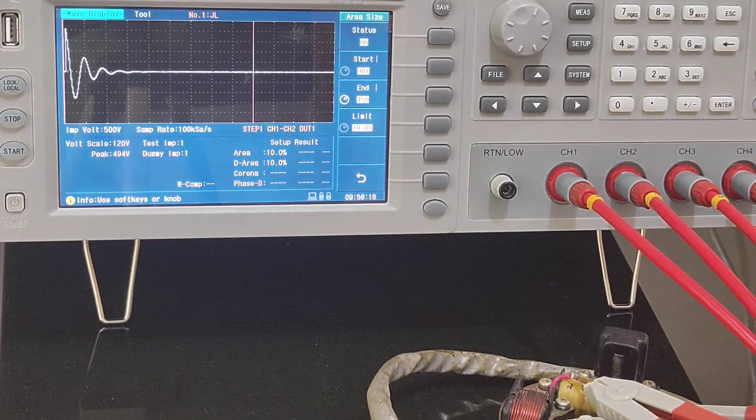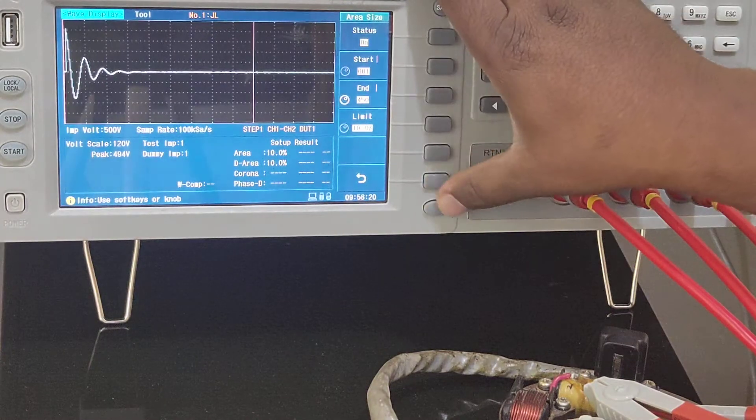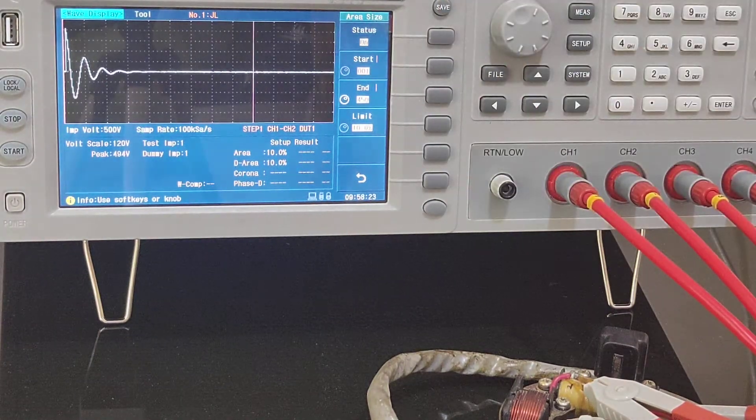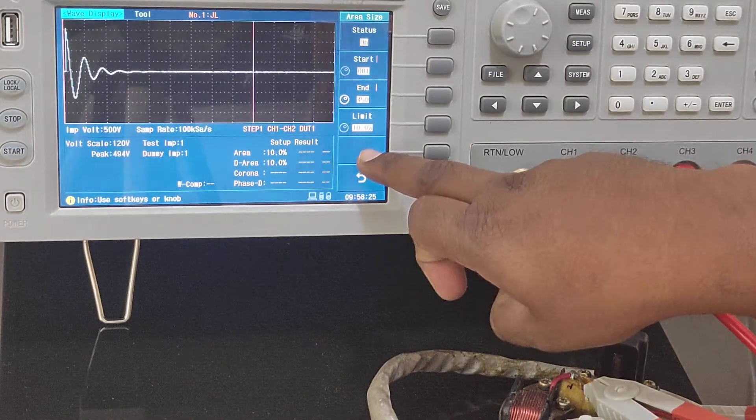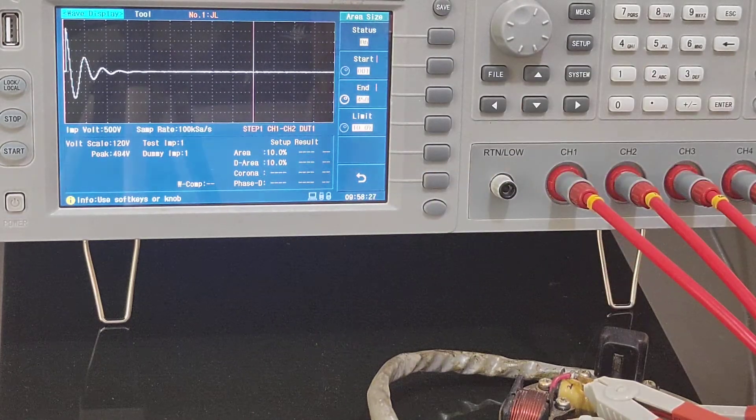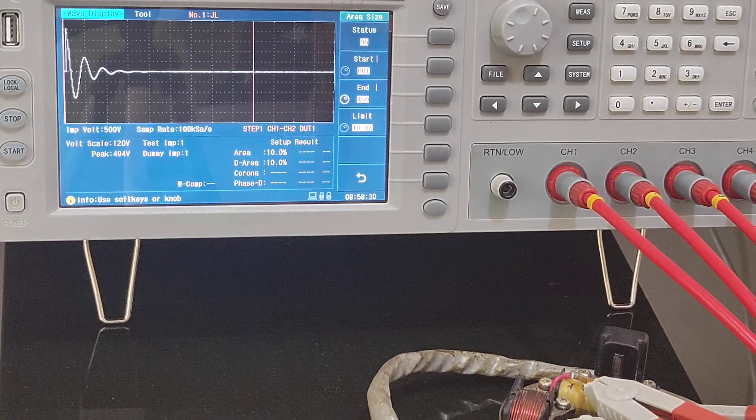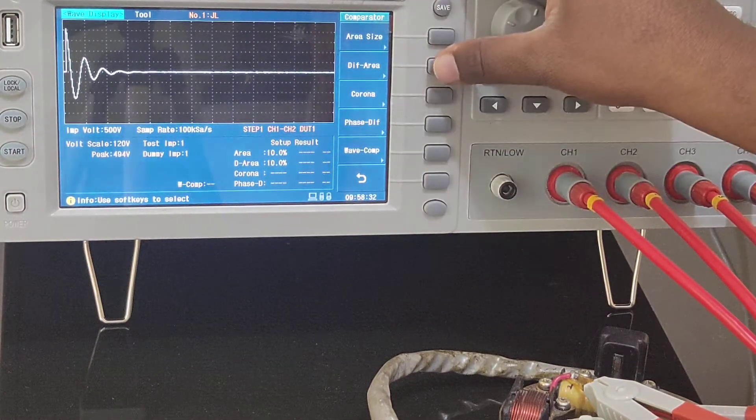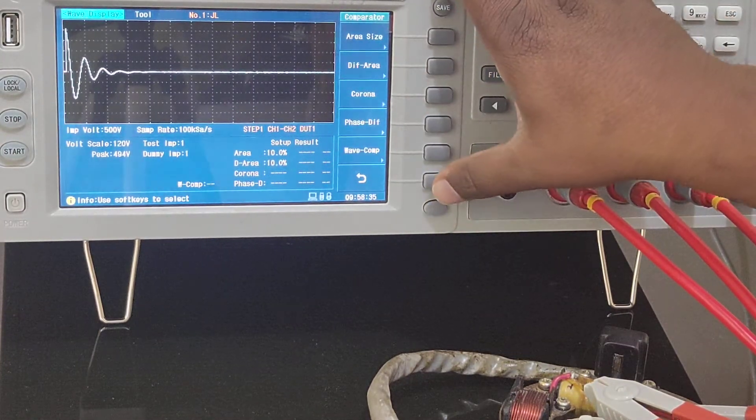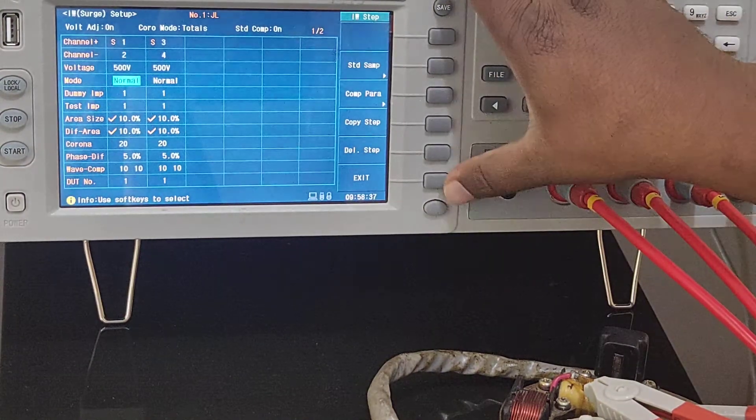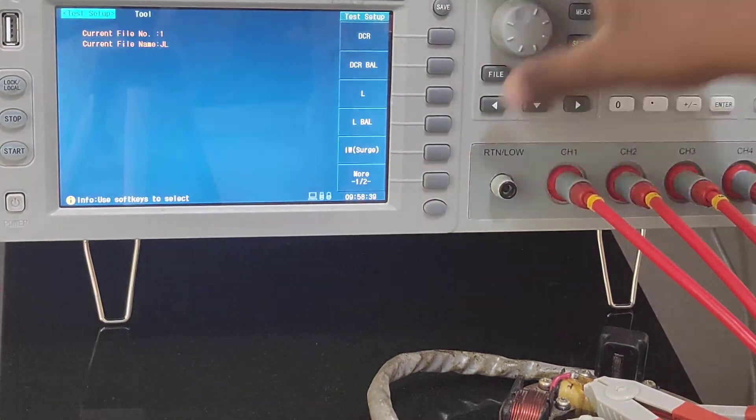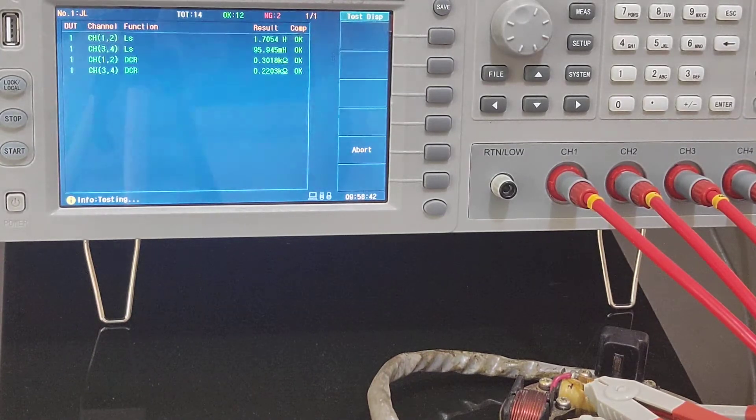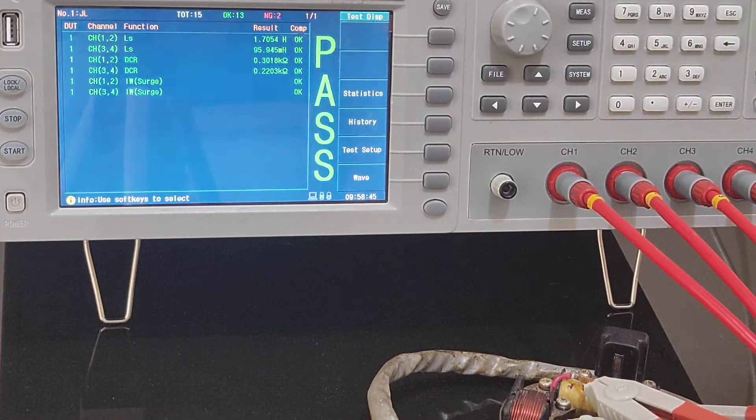And this is the limit - what is the deviation limit. Over here I've given it as 10%, that means in case if the deviation is within 10% it will give you a pass. It's the same way for differential area. After selecting it you simply go to measure test.